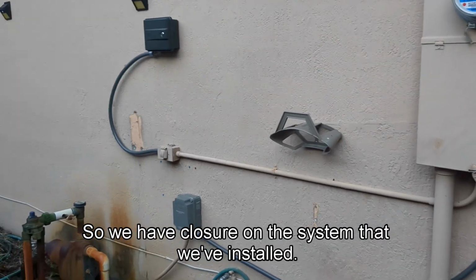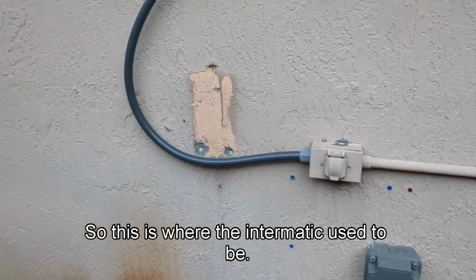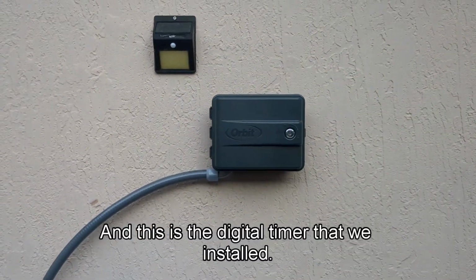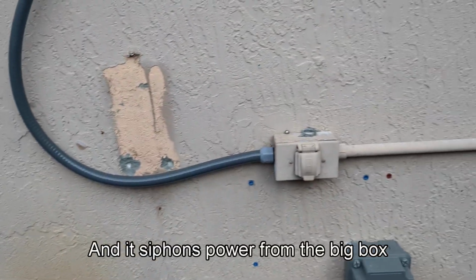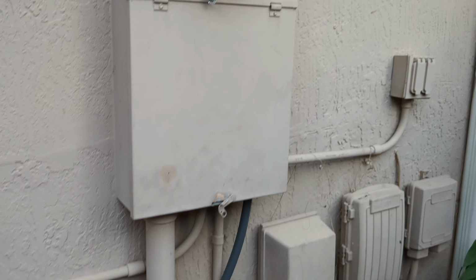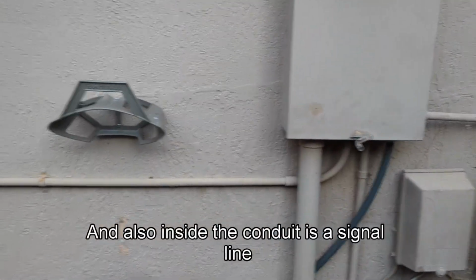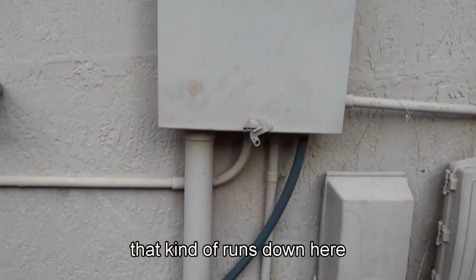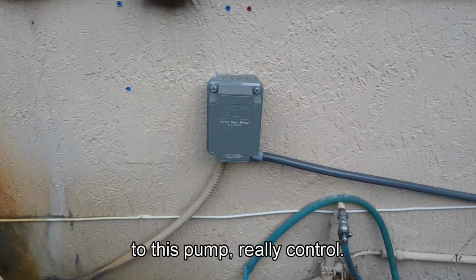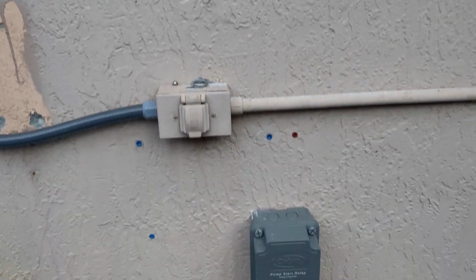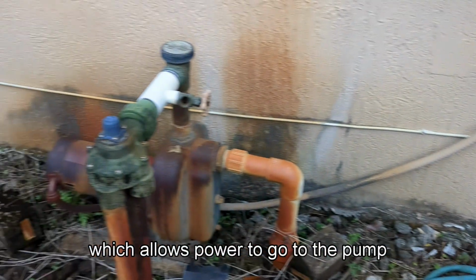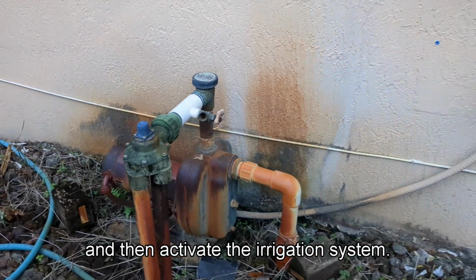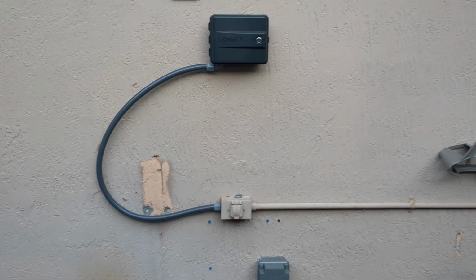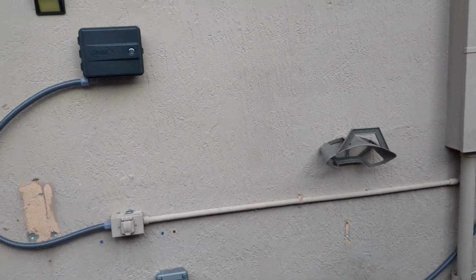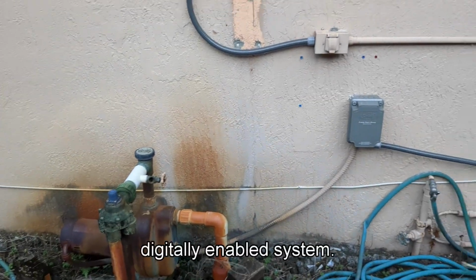All right, so we have closure on the system that we've installed. So this is where the intermatic used to be, and this is the digital timer that we installed, and it siphons power from the big box right here. And also inside the conduit is a signal line that runs down here to this pump relay control. So now this device controls this device, which allows power to go to the pump and then activate the irrigation system. So this is how you would modify an existing pump system into a digitally enabled system.